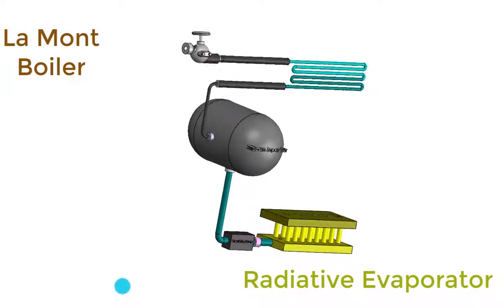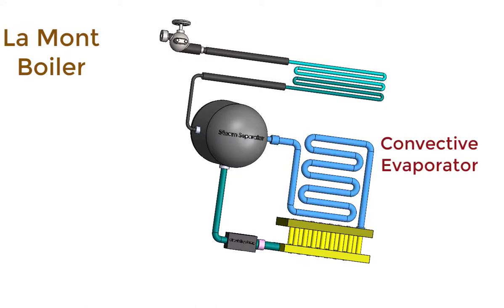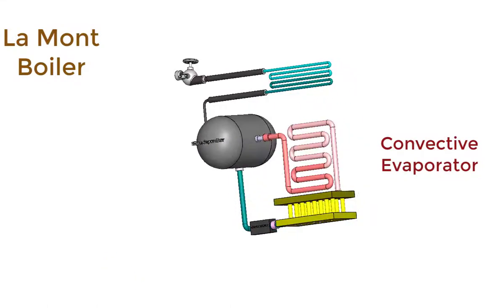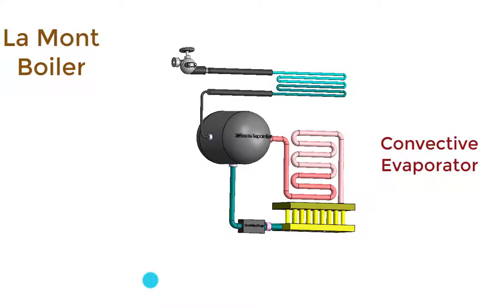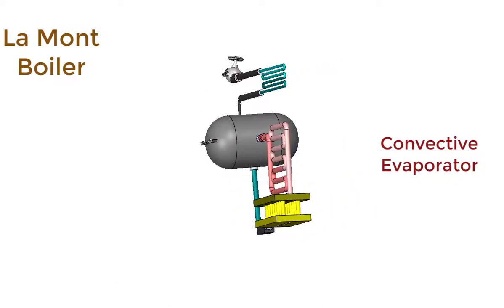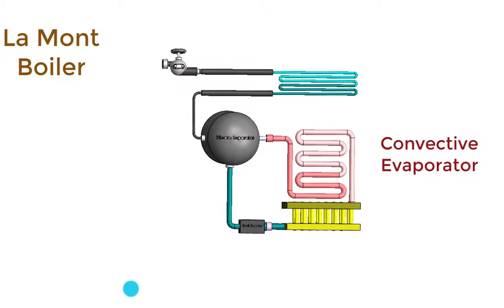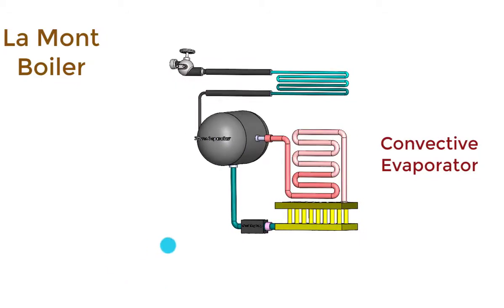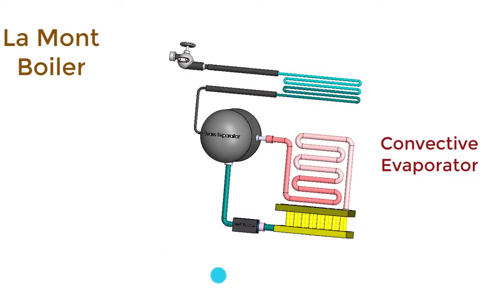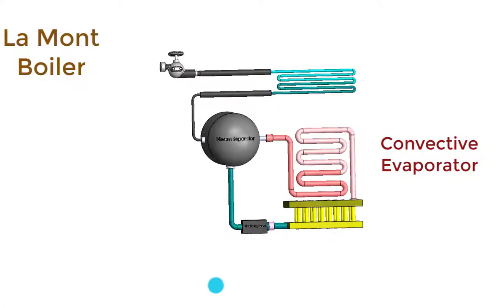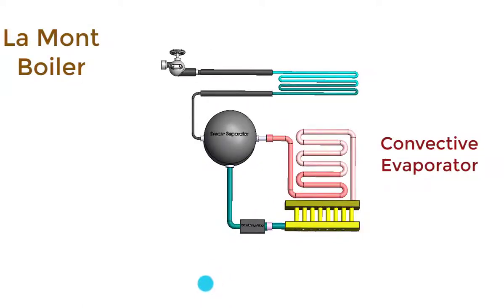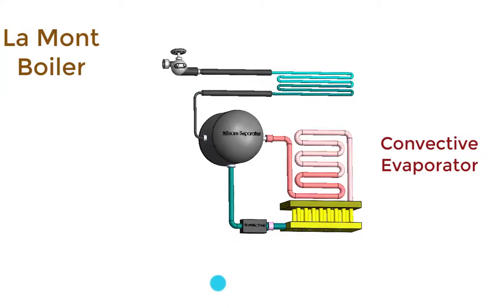After radiant evaporation, it moves to the convective evaporator. Water and steam mixture coming out of the radiant evaporator enters the convective evaporator tubes. In the radiant evaporator, some of the water is converted to steam, so the mixture of water and steam enters into the convective evaporator. The hot flue gases passing over the evaporator tubes transfer a large portion of heat to the water by convection. During this time, the water-steam mixture passing through the convective evaporator is completely converted to steam, and that steam enters into the steam separating drum again.